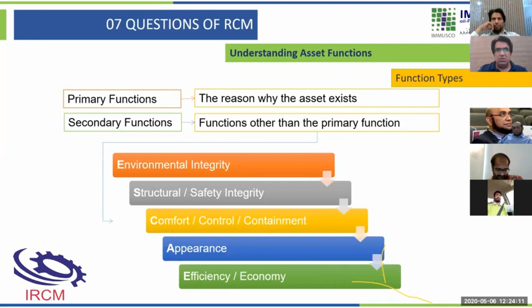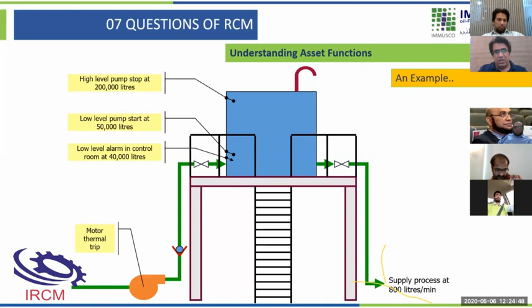For example, you can see low-level alarms in control room at 40,000 liters, low level pump starts at 50,000 liters, high level pump stops at 200,000 liters. So these sorts of activities you need to properly identify, and then you can define the asset requirements, what you actually want from that. Typical functions can be to supply minimum 800 liters of water to the downstream process. Now what will the desired standard of performance be? It will be 800 liters. That is the key thing. If 800 liters is being met, I should not be bothered. But if 800 liters are not being met, then it's a failure state.